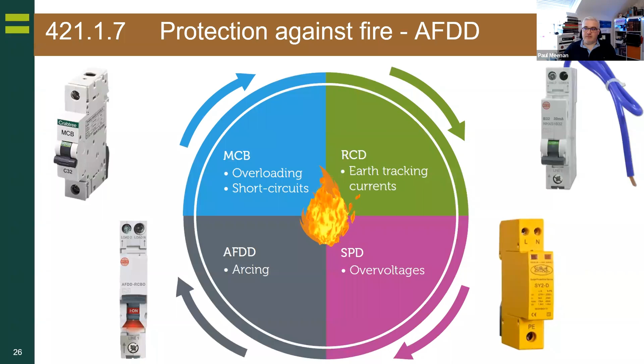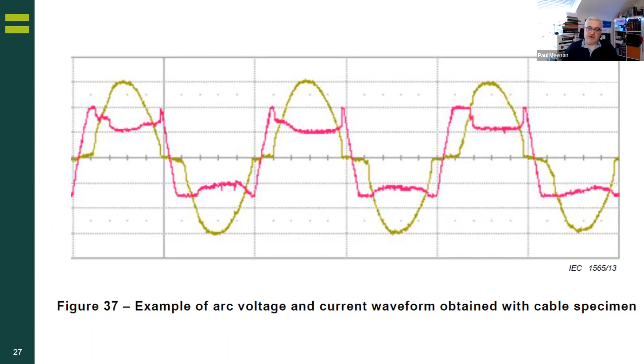So it's just a quick example: there's a standard 50 Hertz waveform, and that's an arc voltage and current waveform that was under test, which we actually did at the laboratory. It shows you some of the noise that can occur on the AC waveform, and the devices are sensitive and intelligent enough to determine whether it's a fault which can cause harm, or a normal operating inrush, surge or interference from a connected load. And that's only 3 cycles of 50. So there's some serious intelligence in these devices.